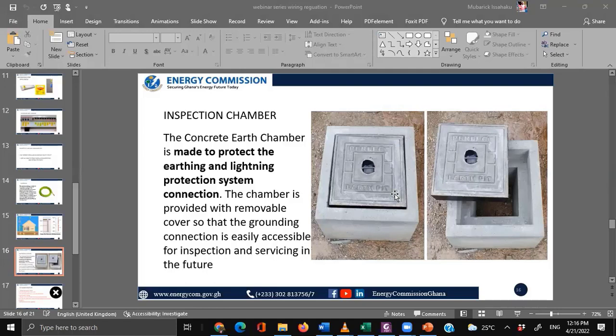But technically, and the engineers on the platform here would bear with me, it's very difficult to get 0 ohm when it comes to earth resistance. So what then can you do? So we've had another provision that if your earth resistance is not 0 ohm and below, and it starts from 1 to 50, then you can maintain the earth, but you have to add an RCD.